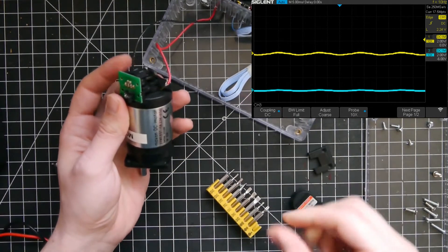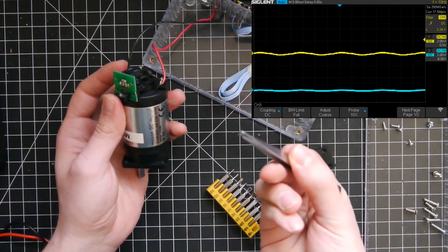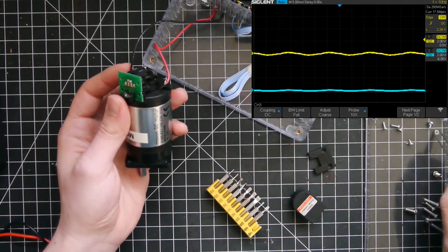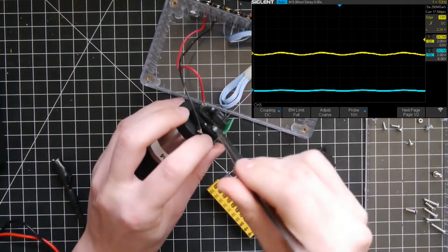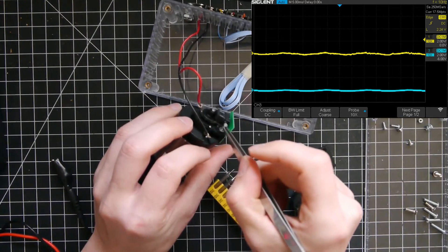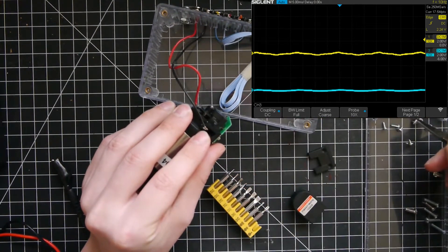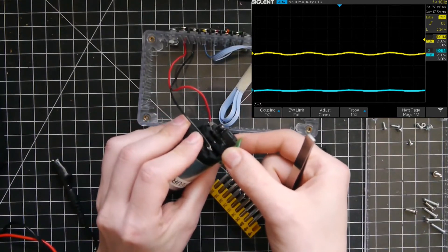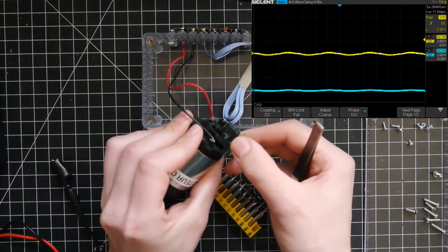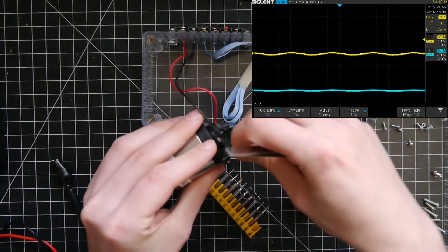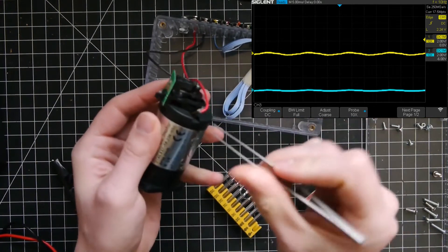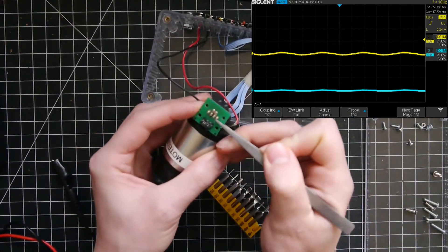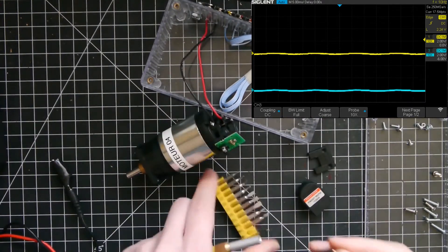And it is actually quite possible to destroy the circuit by, for example, subjecting it to a voltage on terminals for which it is not intended, for instance to switch the power supply line and ground by accident, or to send a voltage too far beyond 5 volts. A simple misconnection like that can very easily destroy the circuit, so it's pretty common. We've had a few occurrences of these issues in the past with this type of encoder, so I was actually pretty sure from the beginning that the problem was coming from this circuit.